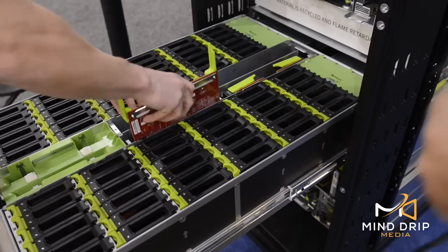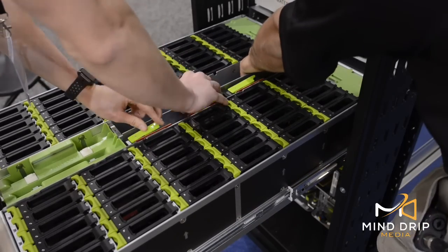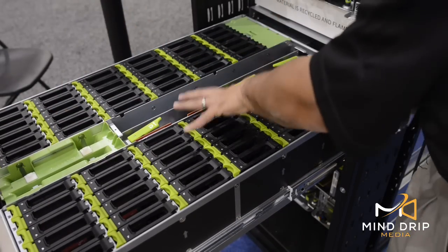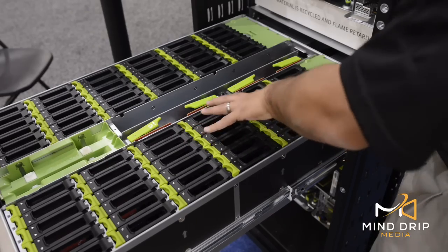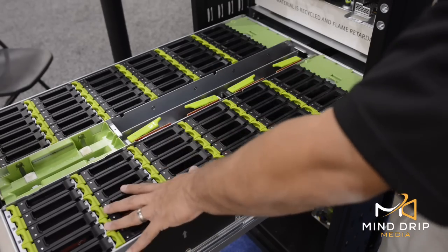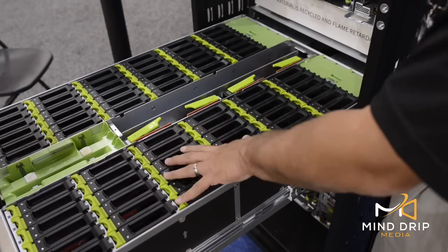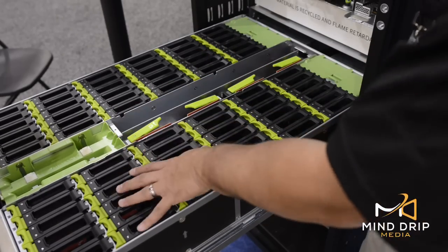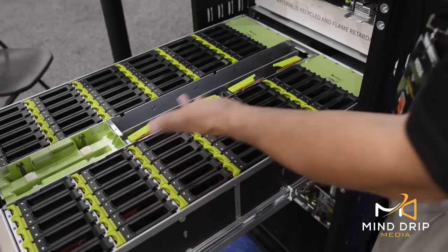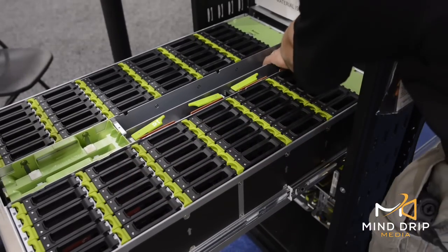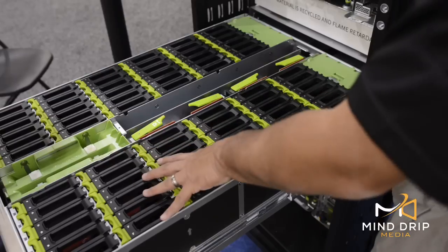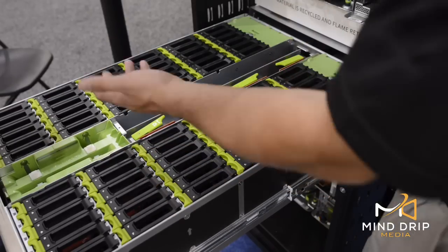Now the interesting thing about this cable unit that's rolling up and rolling out is that this unit can actually stay powered on as it's being serviced. So as it rolls out, we talked to you earlier about the power rail that runs underneath for some of these units. This would not work in this particular case because of the sheer power requirements to run 72 disks. So they actually run separate cabling inside of here so that this unit can stay powered on as it's being de-racked.